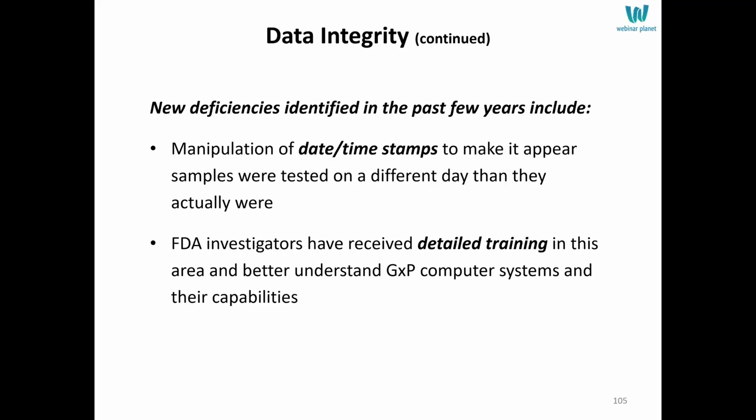Date and time stamps are also important because if you have a server in the cloud or an on-premise server, usually the date and time on the server is synced up with Meridian or Standard Time. But if you have a legacy system in a lab or manufacturing area and you have software loaded onto a local device running that particular piece of equipment or instrument, then the application software is going to take the date or time from the local device. And you must make sure that the date and time for that local device is locked down and no one can change it.